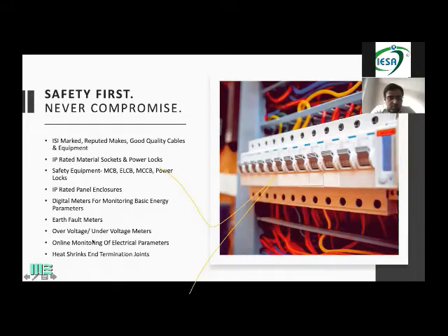Online monitoring of electrical parameters, it is the future. So what is online monitoring? This is what we are trying to do in the coming months. Normally, everybody is concerned about how much load the genset is giving. What we want to achieve is what we call smart distribution panels. All our panels are equipped with a GSM card. Wherever the panels or my main distribution boxes are going, they are equipped with a card which tells me the whole monitoring of the energy.